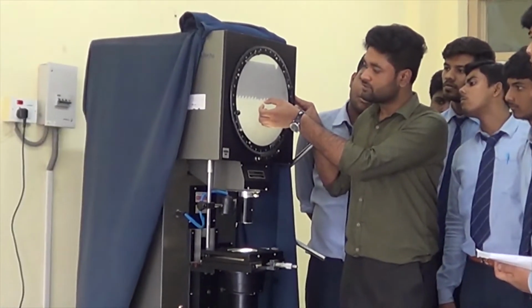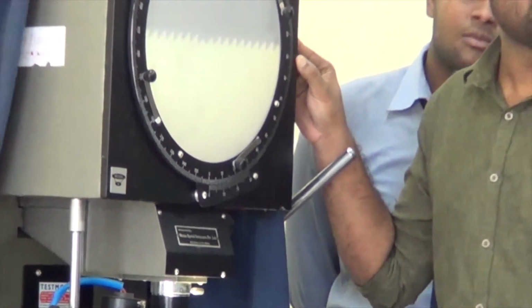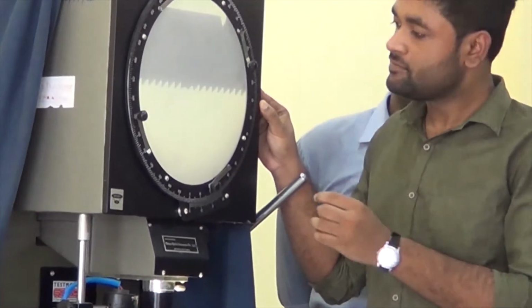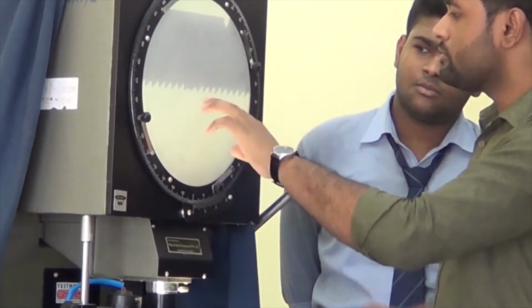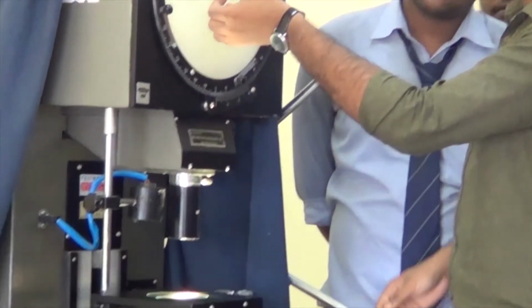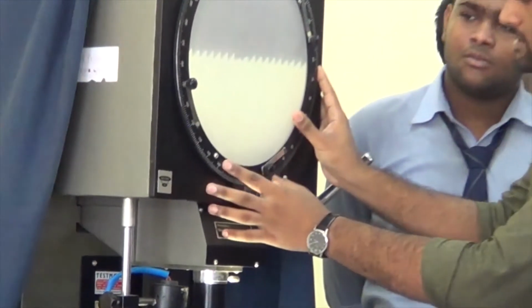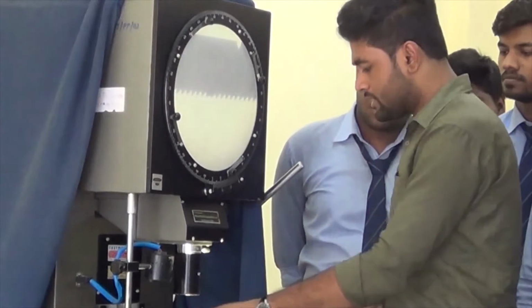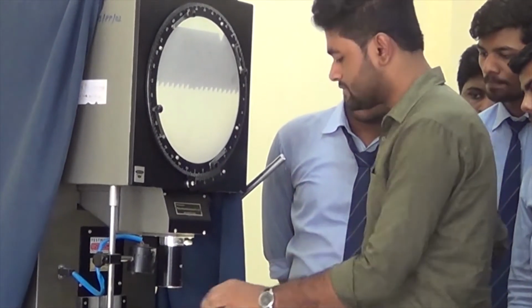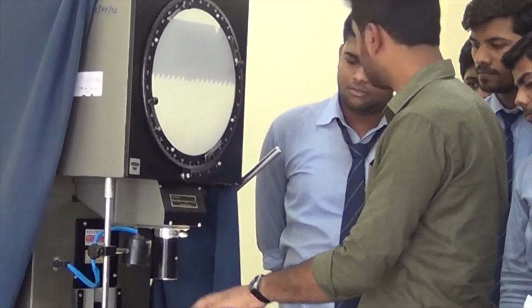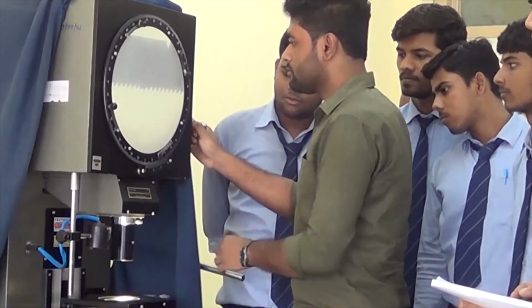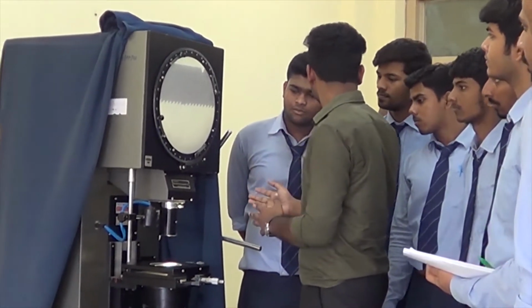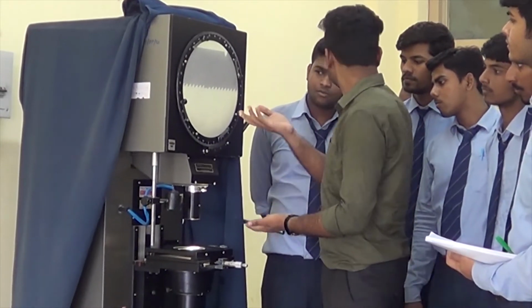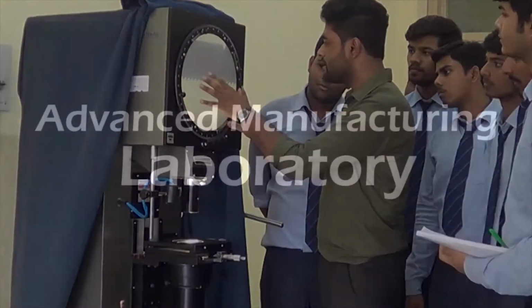Therefore, the XY axis of the screen can be aligned correctly using a straight edge of the machined part to analyze and measure. This projection screen shows the profile of the sample and is zoomed for better ease of computing linear dimensions. An edge of the sample to analyze can be aligned in the grid on the screen. After that, basic measurements can be obtained for distances along with other points. This is being carried out on a zoomed profile of the specimen. It is easier and also lessens mistakes when measuring on the magnified projection screen of a profile projector.